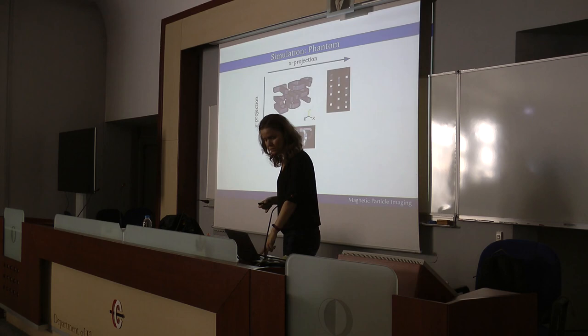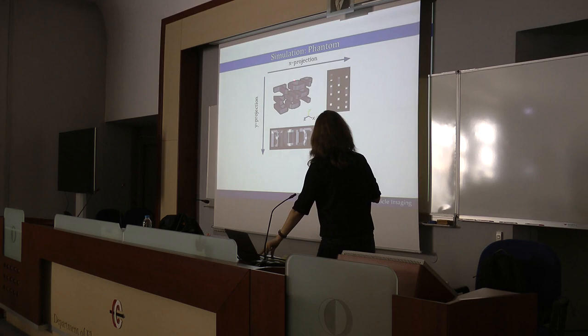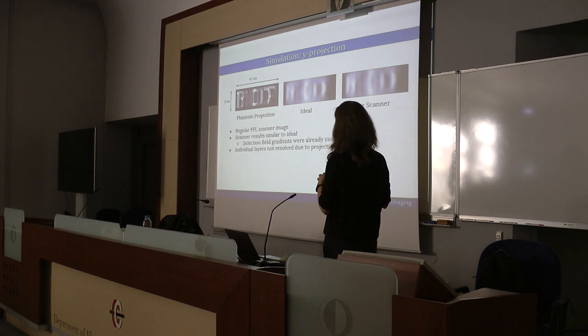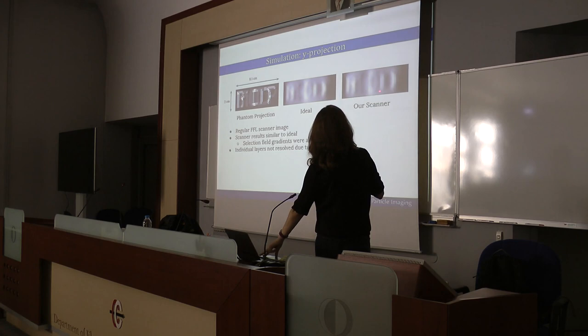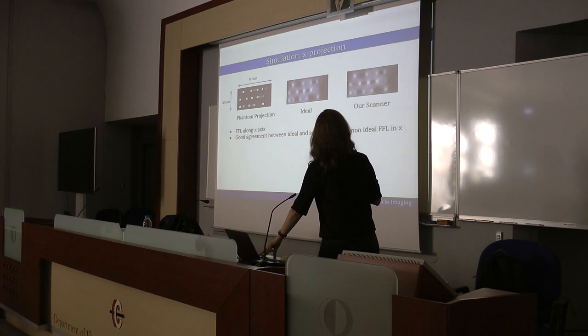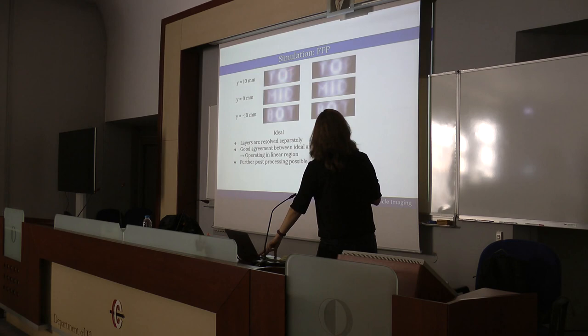This is a simulation demonstrating the principle of the scanner. For a phantom made of three layers filled with nanoparticles, the projection along x should look a certain way, and along y another way. Simulations using the magnetic fields of our scanner show that with ideal fields we should get a signal blurred by the system response due to x-space reconstruction; with our scanner specifications, we expect images very similar to the ideal. We can then turn on FFP mode for individual layer-by-layer imaging.